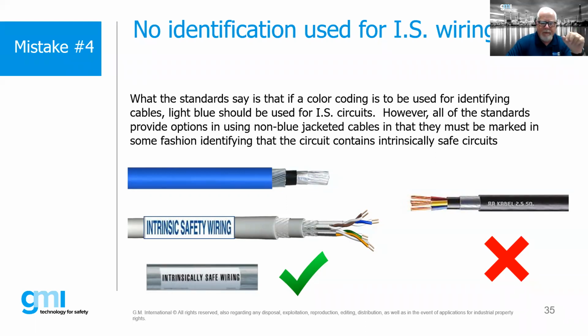Say we have a two-pair cable and then we have a shield. We would take that shield, use some sort of shrink tubing or mastic or something like that to protect it, and generally leave it floating in the hazardous area. However, we would take that shield all the way back and tie it into our normal ground. The reason we don't want to tie it in on both ends is that we could potentially create an antenna, which we don't want to do. So we want to tie it into our safe area ground, in our control panel at that point - that's our general means of dealing with the ground.